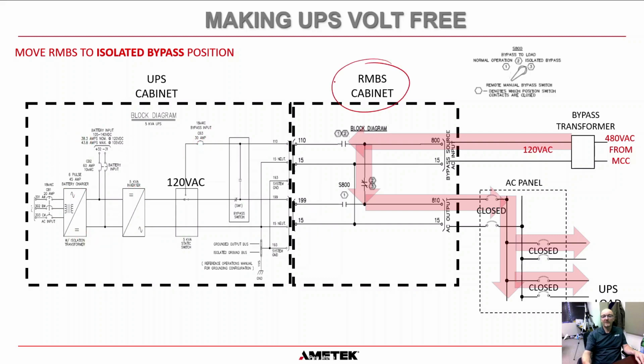Okay, that is why the RMBS cabinet is a very, very good idea. And like I said, you can have an AMETEK SCI RMBS cabinet installed on the output of any manufacturer of UPS. They're not directly linked. You don't have to have one particular manufacturer of bypass switch for one particular version of a UPS. The RMBS cabinet does have some options that connect back to the UPS and give alarms. But for the standard, being able to make your UPS volt free, you can use an AMETEK SCI RMBS cabinet on any UPS manufacturer that's out there. And as I said, all terminals on the UPS are now volt free.